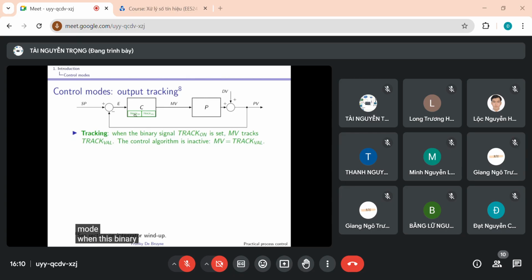When this binary signal here, track on, is set to 1, then the controller output MV will track the value here, track value. This is a signal that can be chosen by the one that is programming the control algorithm. When track on is set to 1, the control algorithm is inactive, and as I said, MV is equal to track value. I said that the control algorithm is inactive, but this has to be done in the proper way in order to prevent integrator windup.